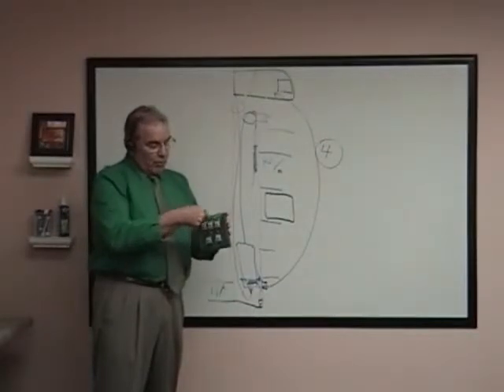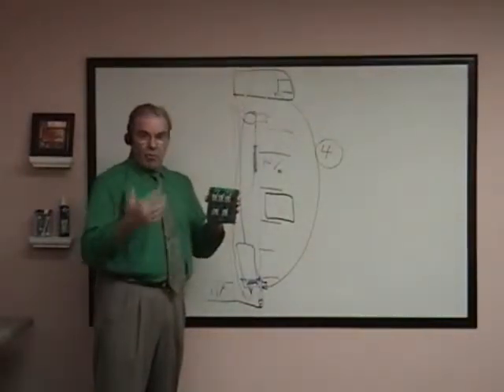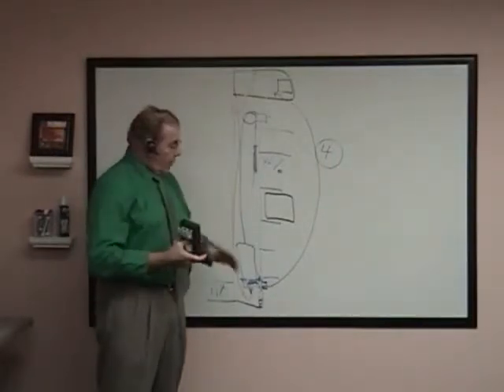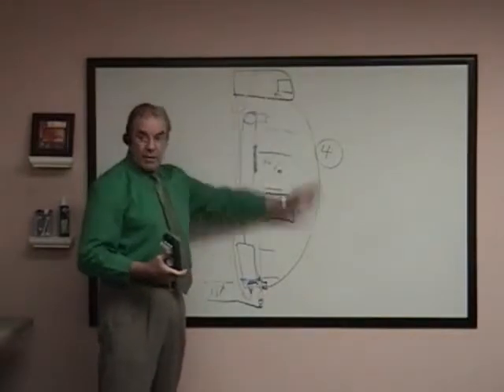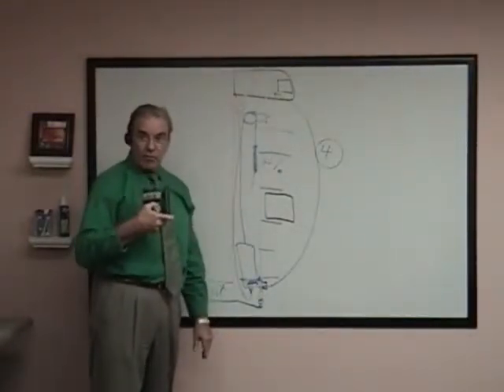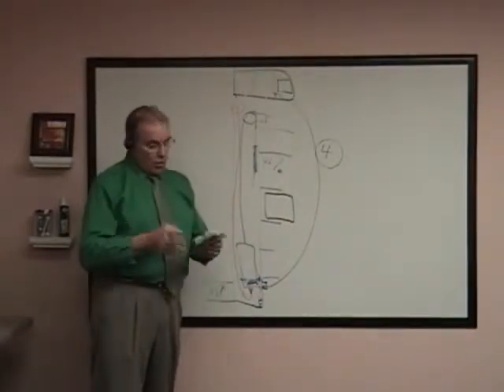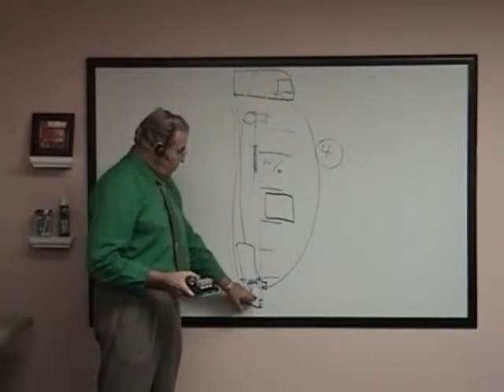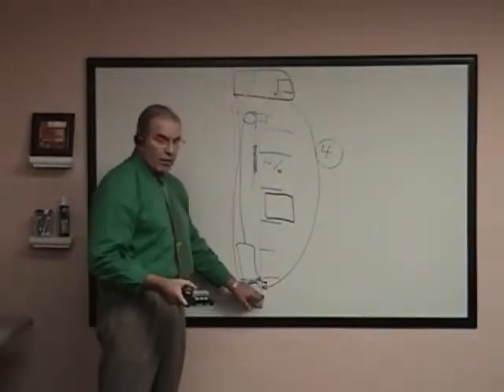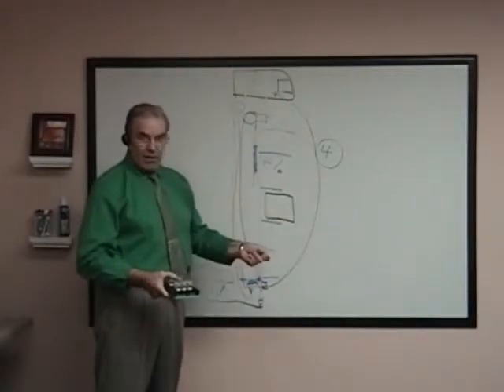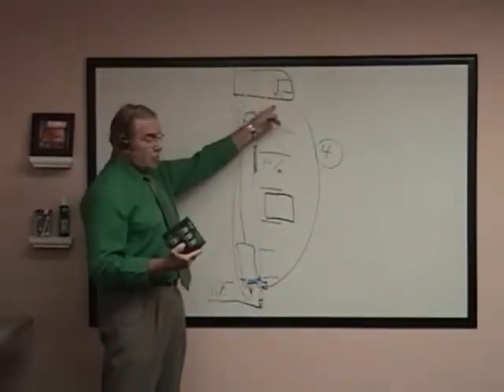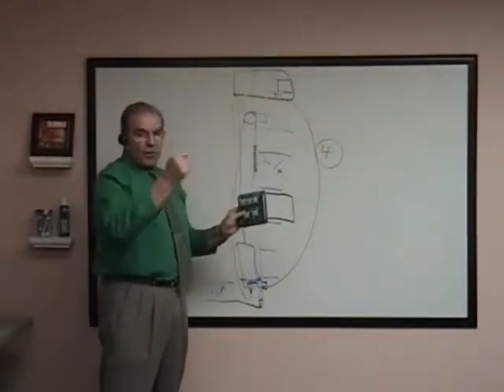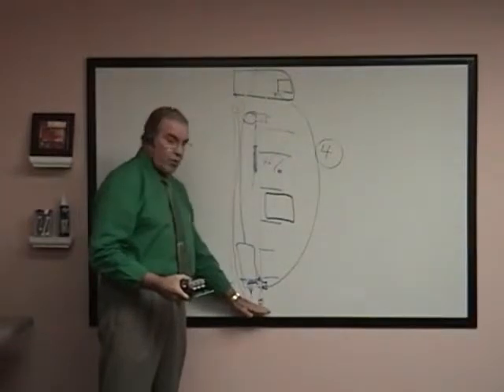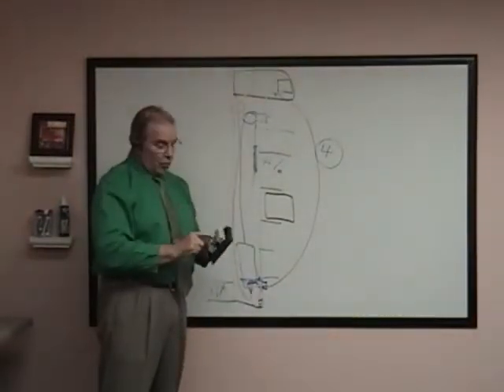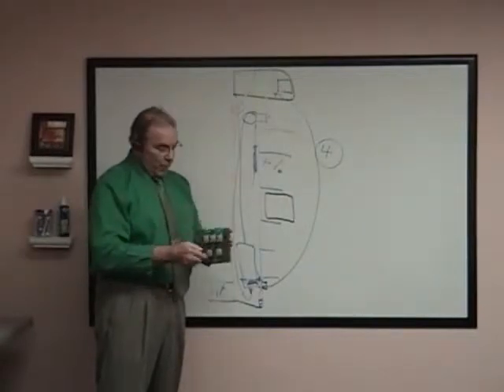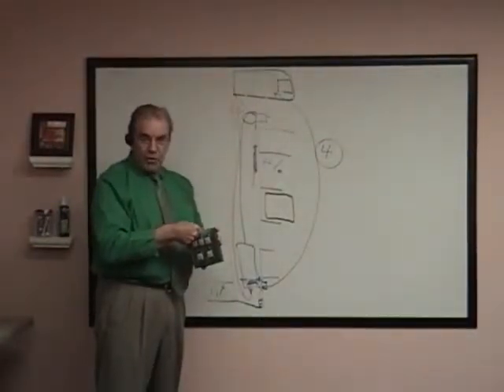That may not be palatable for him. So by moving a jumper on this board from the A position to the B position, that removes the automatic holding circuit. So that once the switch is reset, the elevator should go back into operation on its own without ever going to reset the system from the machine room. So we give them two options. There's a third option we can provide, and that's a reset from the pit switch, which is, every elevator has what they call a pit switch. It's a safety device in the pit, and it's basically an on-off switch for the elevator. We can also wire this board to operate off the pit switch power, so that all you would have to do is flip the pit switch. After you reset your sensor here, and you've removed the liquid, you could just reset the pit switch, and that could reset this board, depending on how we hook it up. But he's always got this automatic reset option, if he chooses it.